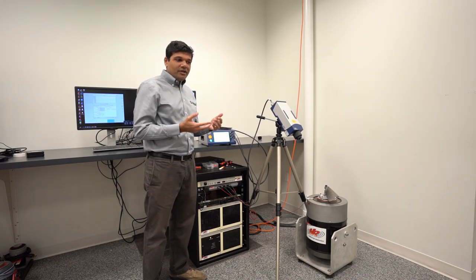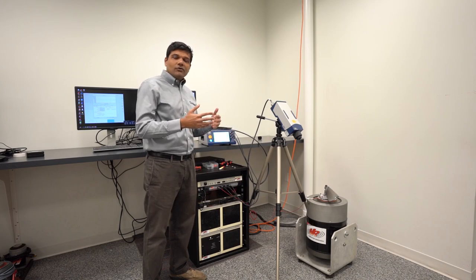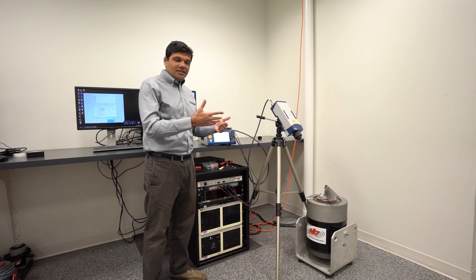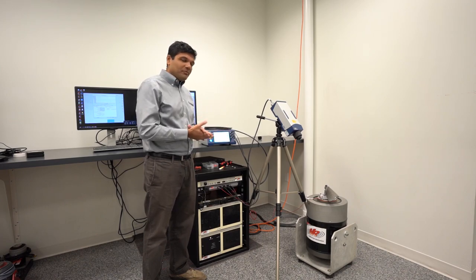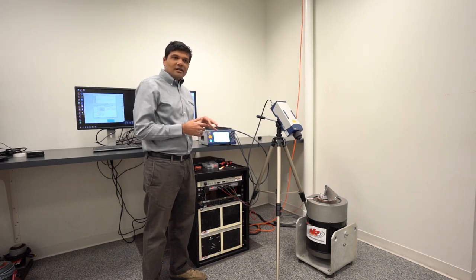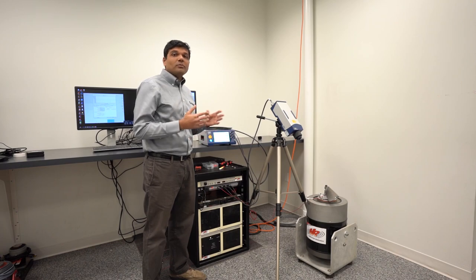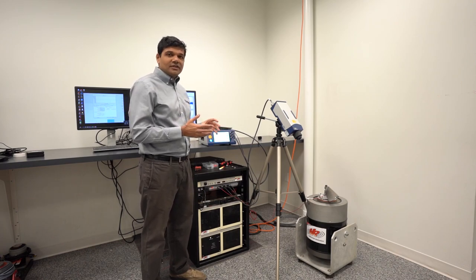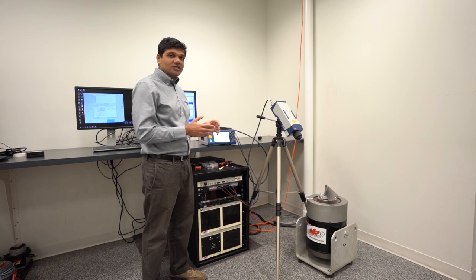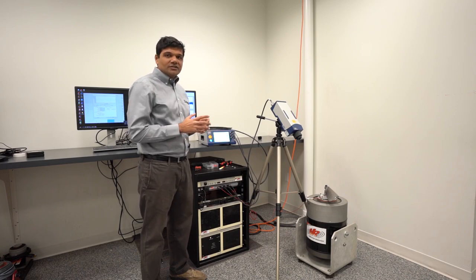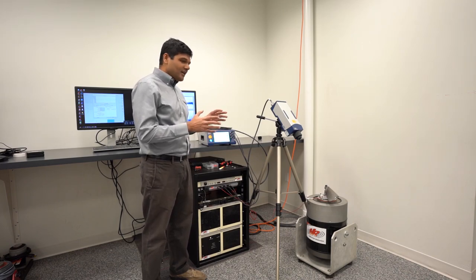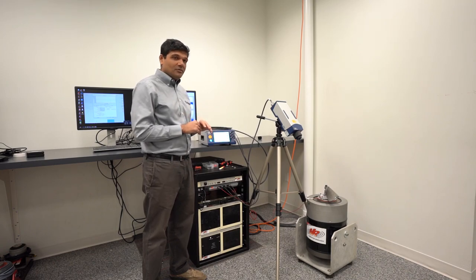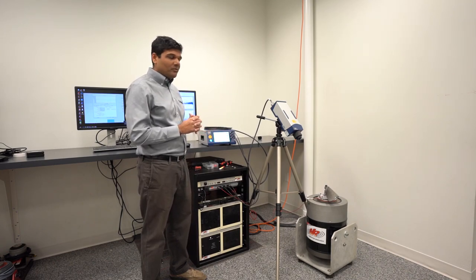Fundamentally, the way it works is laser Doppler effect. We are looking for any change in the optical path distance between the sensor and the vibrating object. That change in the optical path distance causes a Doppler shift. And the Doppler shift is directly related to velocity or displacement, which is one of the misconceptions, or the questions: what are the primary quantities coming out of a vibrometer.